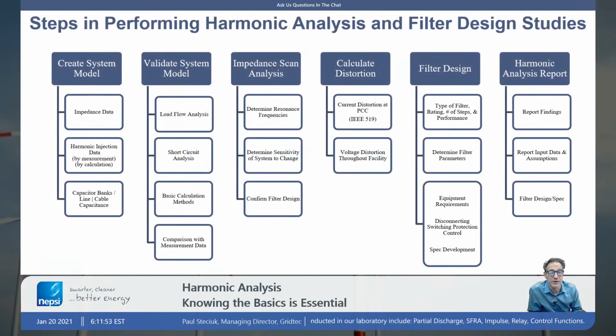Oftentimes it takes a lot of experience to know what can be built and what cannot be built. So there's a lot of steps in performing harmonic analysis. All the programs that are out there nowadays, you can do load flow analysis, short circuit analysis, and a package is added on to do harmonic analysis. So much of the same data is used in the harmonic analysis to do load flow as it is in harmonic analysis. Really the key things in a harmonic analysis is you need to know the nonlinear load data, the harmonic current injection data, and then the impedance data of the network.